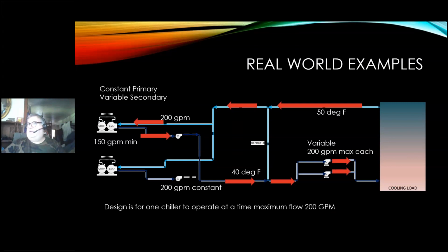But somebody changed the settings on the pressure out there in the system to run the second pump. So now I've got 400 GPM pumping through the building, and I've got 400 GPM coming back to the plant, but I've only got 200 pumping through the primary. Where does that other 200 go? The other 200 of 50-degree water gets pumped back into the loop of my 40-degree water.